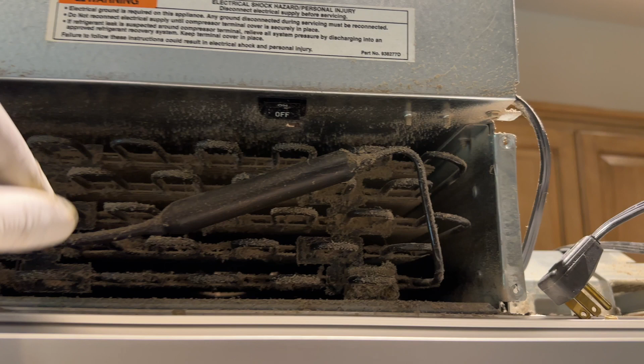Every time you do a sealed system repair, you need to replace the filter dryer, which is this piece. Since this one has been more than 20 years, we definitely need to replace that.